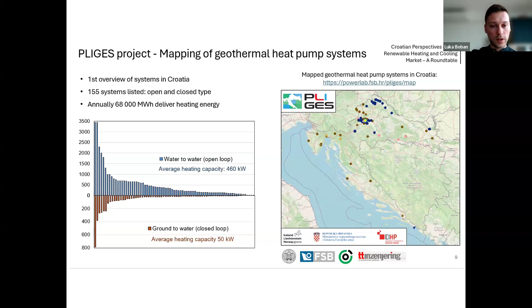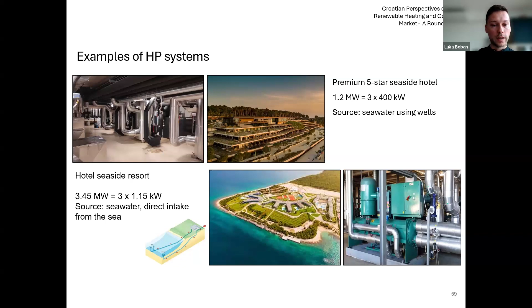Ground-to-water or ground-coupled heat pumps don't have such large capacities, but are also used in different kinds of objects. Such systems are ideal for buildings requiring high specific demand, like in tourism, or in culturally protected buildings where you don't have the option to significantly improve the building envelope. We have a lot of hotels on the seaside using seawater as renewable energy, either using wells or with direct intake from the sea.